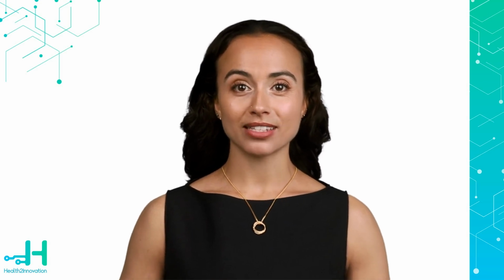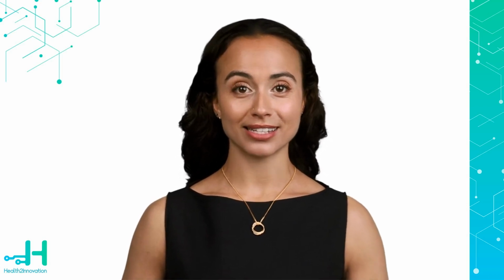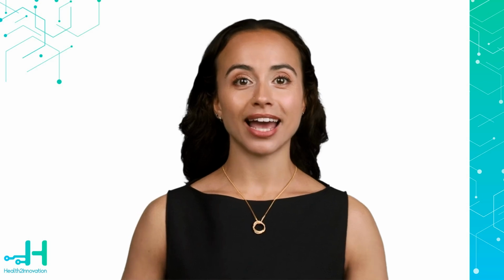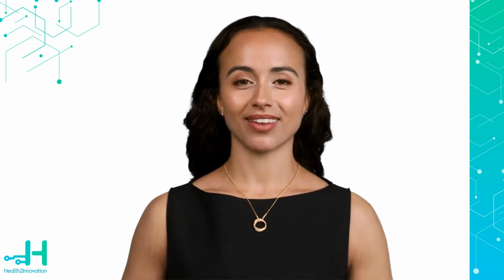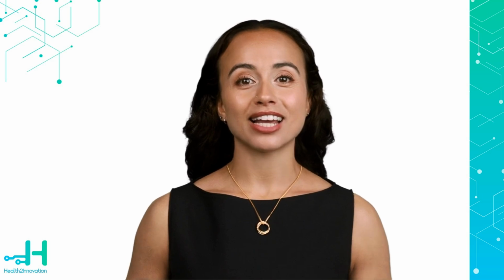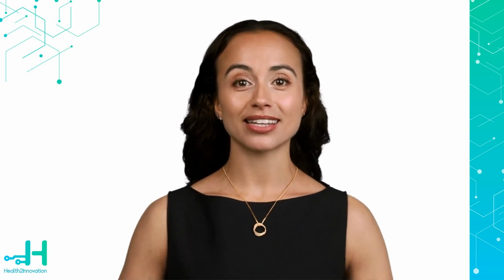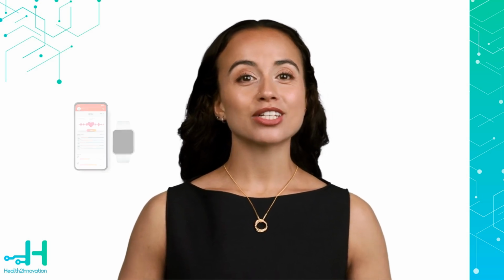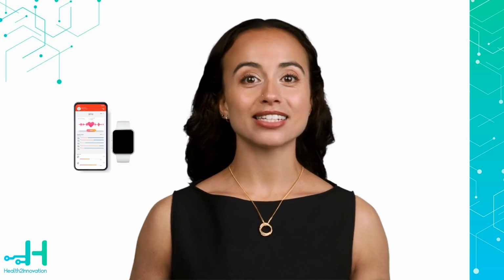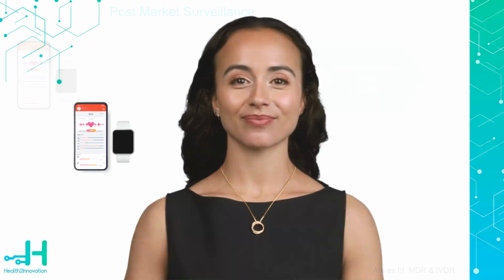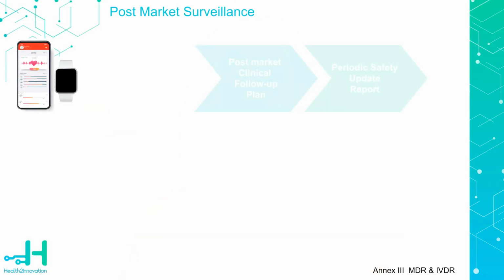But it isn't just your own device you should consider. Devices of a similar nature or that utilize similar technologies may also be of interest, and this additional data can sometimes be used to support or justify decisions for action or inaction by a manufacturer. Annex 3 outlines in detail the new requirements to be included in the technical documentation to comply with MDR. Using our smartwatch app as an example, let's dive deeper into this area. It all begins with a plan.